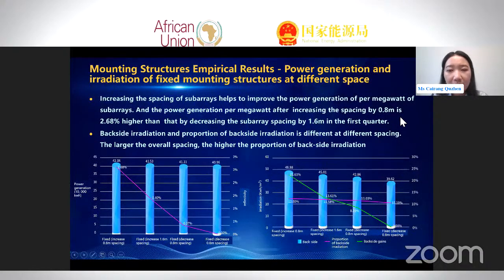For the mounting structure practical results, we can see the power generation and irradiation of the fixed mounting structure at different spacing. Increasing the spacing of subarrays helps improve the power generation per megawatt of subarrays. The power generation per megawatt after increasing the spacing by 0.8 meters is 2.68% higher than that after decreasing the sub-area spacing by 1.6 meters in the first quarter. The proportion of backside irradiation is different at different spacing: the larger the overall spacing, the higher the proportion of backside irradiation.